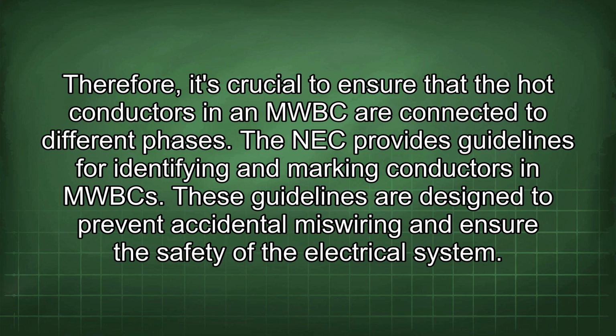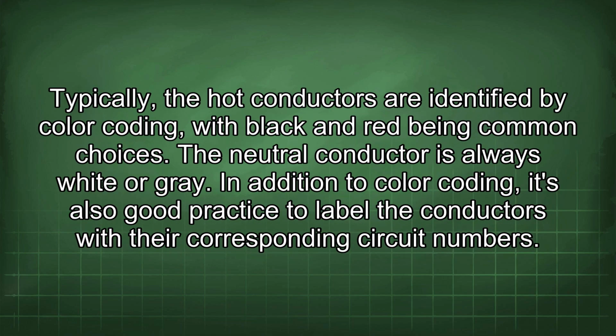The NEC provides guidelines for identifying and marking conductors in MWBCs. These guidelines are designed to prevent accidental miswiring and ensure the safety of the electrical system. Typically, the hot conductors are identified by color coding, with black and red being common choices. The neutral conductor is always white or gray.